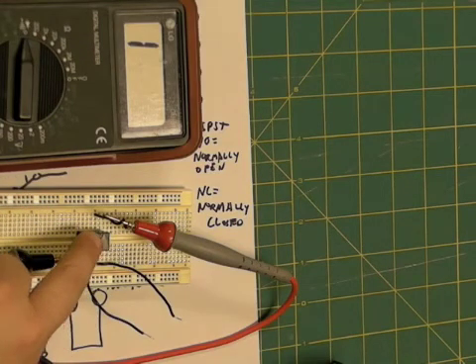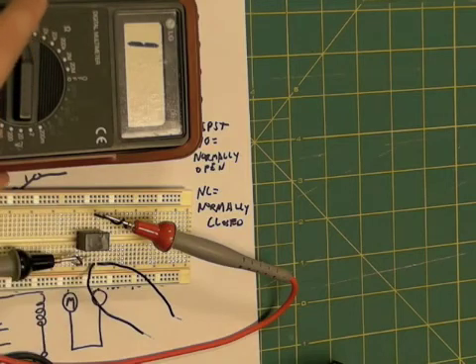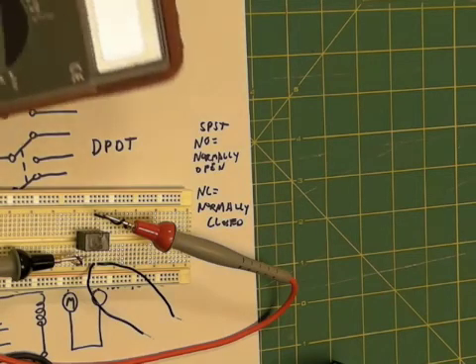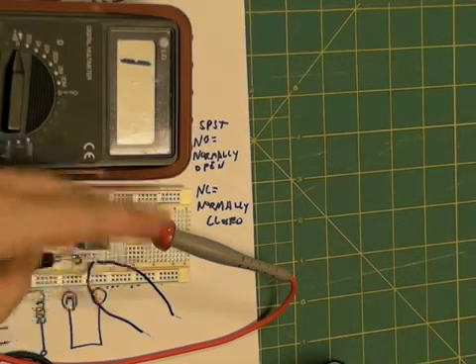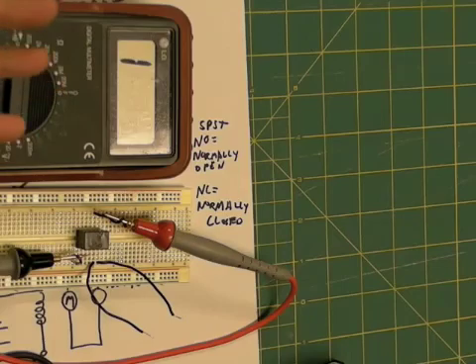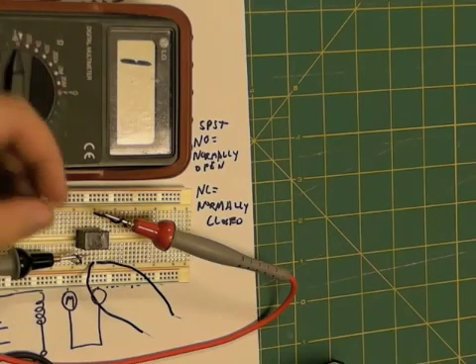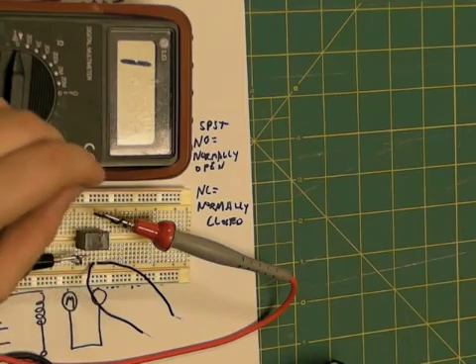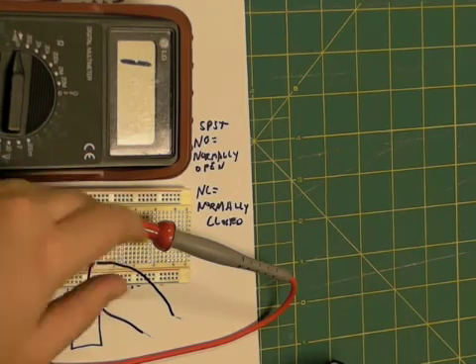Note that these relays can come in just about every configuration we talked about before - single pole single throw, single pole double throw, double pole double throw, etc. Of course, the more leverage you have to move, the more current it takes for the relay to trip. So you always got to look at your specs to see how much the relay needs to trip and how much current the relay can handle.